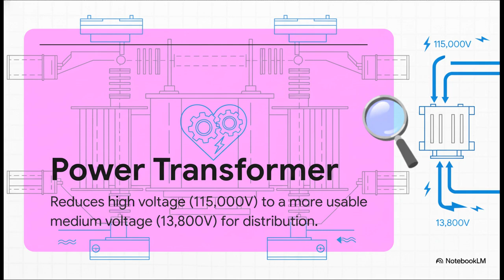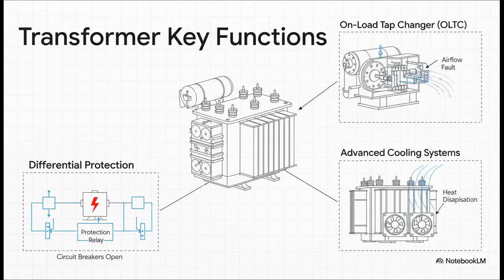Now, this isn't just a simple box. It's packed with sophisticated tech. It has something called an on-load tap changer, or OLTC, which makes these tiny, constant adjustments to keep the voltage perfectly stable. It has advanced cooling systems, basically giant radiators, to deal with the incredible heat it generates. And, most importantly, it has what's called differential protection, which is like a super fast emergency stop. If it senses an internal problem, it shuts everything down in a fraction of a second to prevent a major failure.